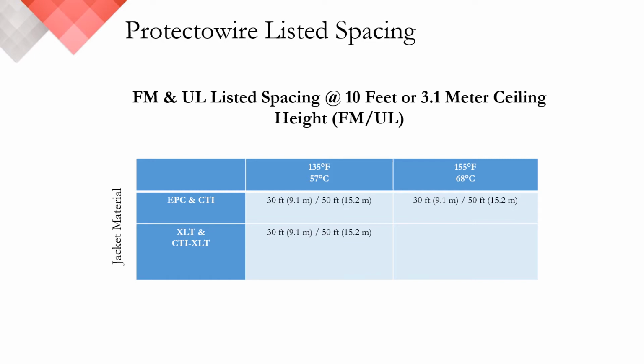As we just discussed, Section 2.3.3.2 of FM datasheet 8-29 references the maximum allowable space for smooth ceilings. For non-smooth ceilings, it references 1/2 the listed spacing or the maximum allowable sprinkler spacing. To provide some context, on your screen is our maximum listed spacing from FM and UL. Our detectors have earned a maximum allowable space from FM of 30 feet or approximately 9 meters on centers, whereas UL allows for a maximum of 50 feet or approximately 15 meters on centers.